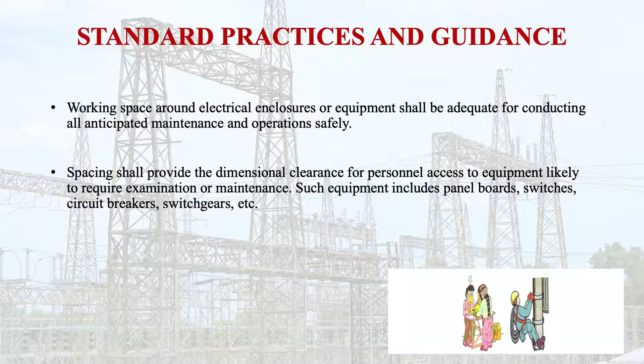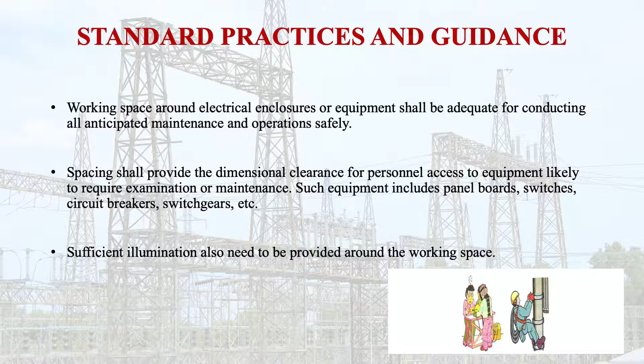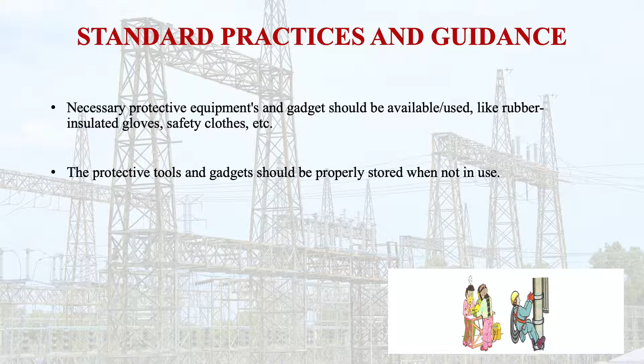So these working clearances are not required for equipment that is not likely to require access, but working space is still required. Sufficient illumination also needs to be provided around the working space, and necessary protective equipment and gadgets should be available and used, like rubber insulated gloves and safety clothes, etc. The protective tools and gadgets should be properly stored when not in use.